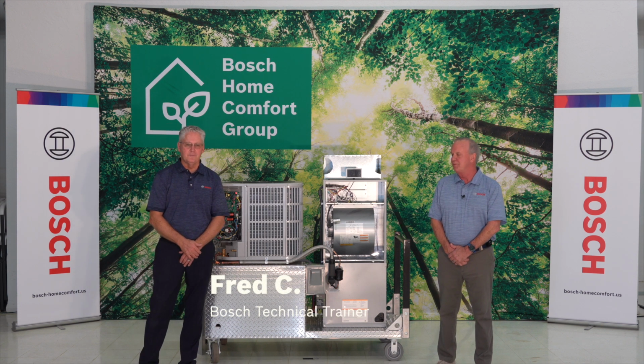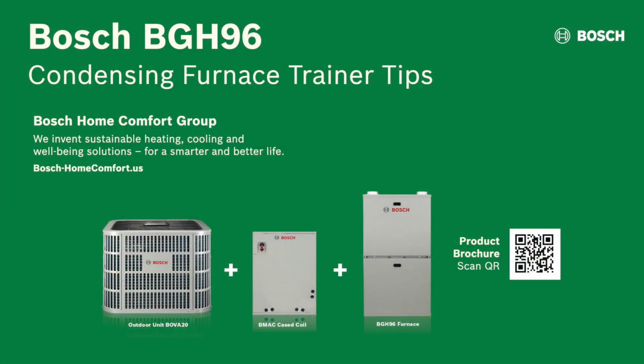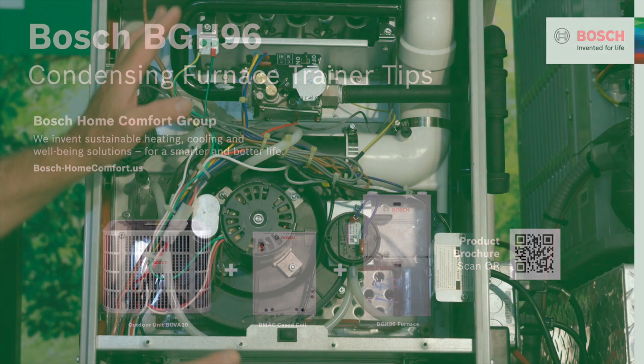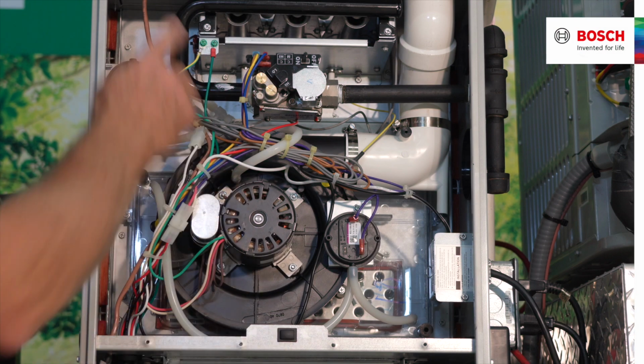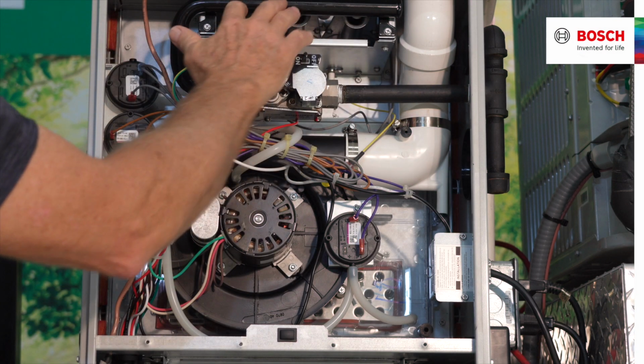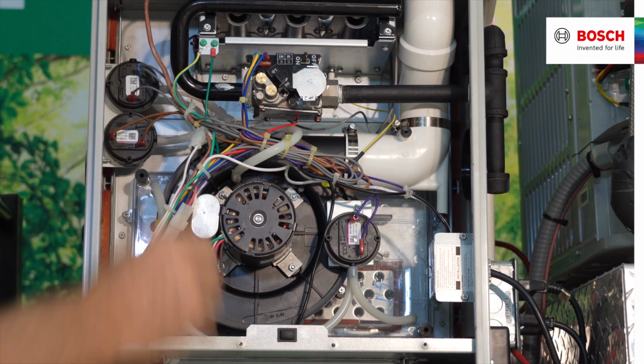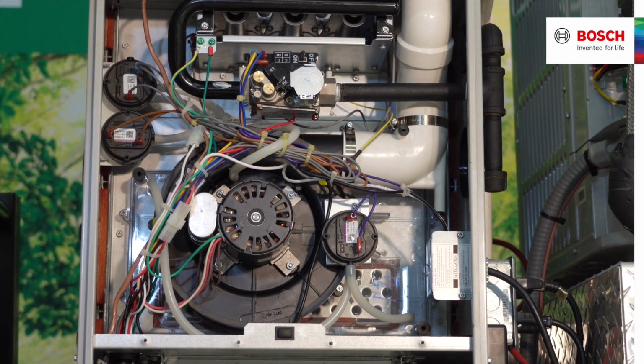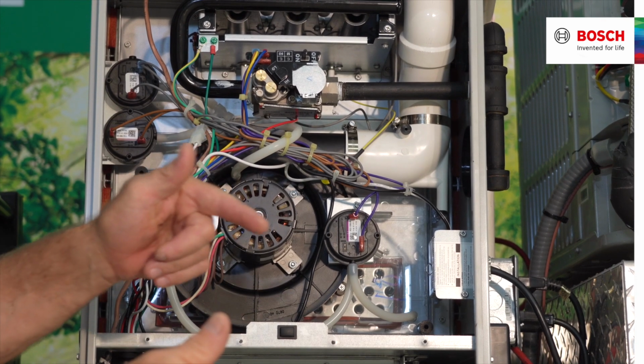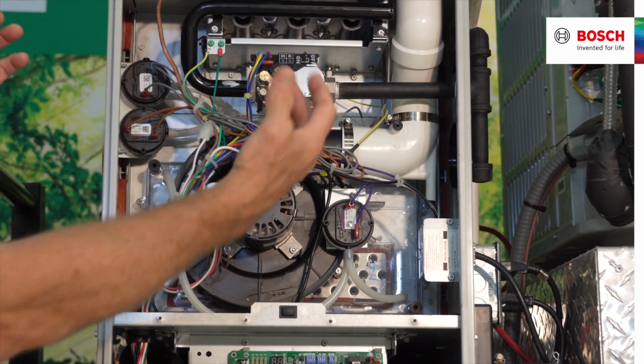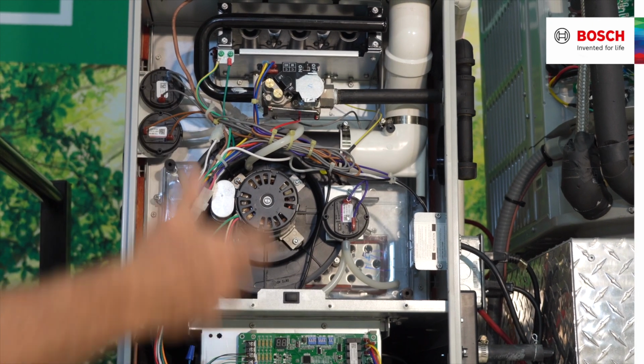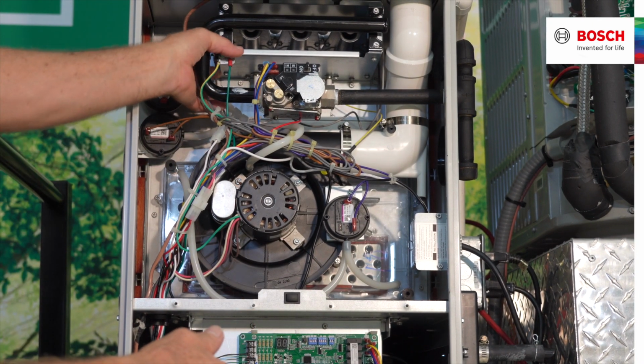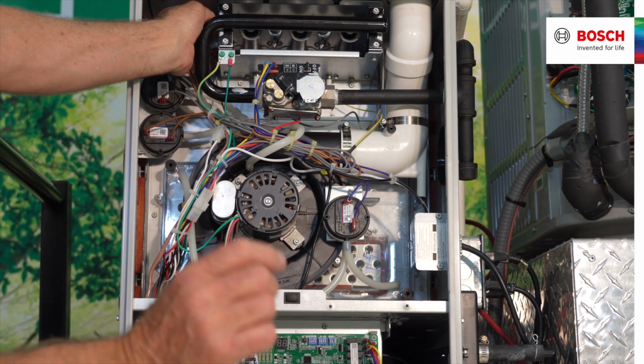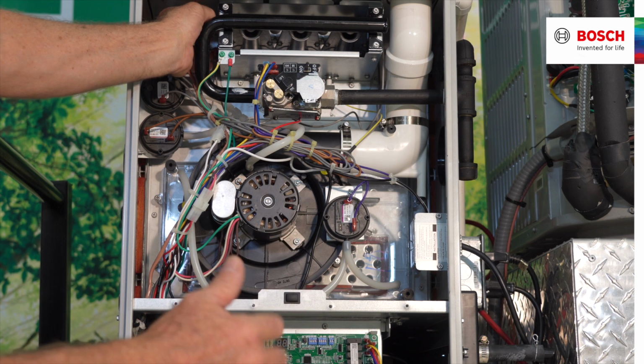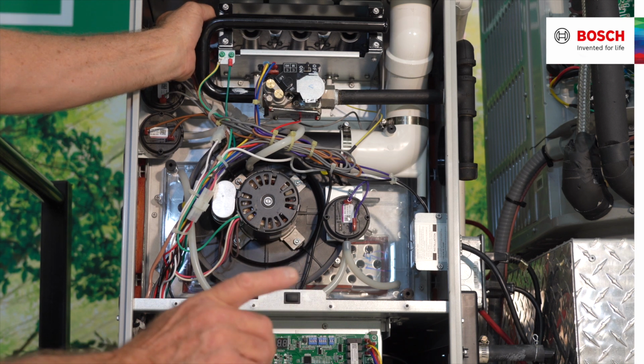And I'm Fred Crick. We're going to take you through the BGH furnace, all of the ins and the outs. I want to show you a couple little ideas about this furnace. On the left-hand side and the right-hand side by the burner section are some limit switches. Those are MRLCs, which means they are a manual reset. So if the flame belches out, whether we're in a horizontal left or horizontal right situation, those manual reset temperature flame control switches will need to be reset. Again, those are a manual reset.